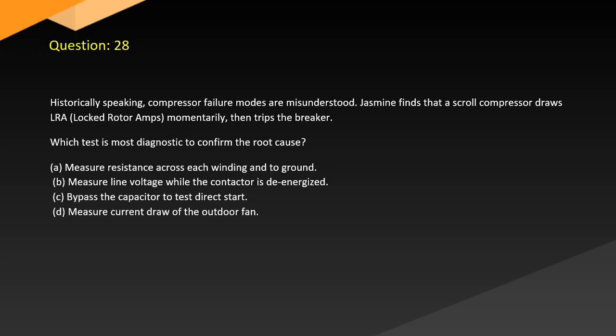Question 28. Historically speaking, compressor failure modes are misunderstood. Jasmine finds that a scroll compressor draws locked rotor amps momentarily, then trips the breaker. Which test is most diagnostic to confirm the root cause? A. Measure resistance across each winding and to ground. B. Measure line voltage while the contactor is de-energized. C. Bypass the capacitor to test direct start. D. Measure current draw of the outdoor fan.